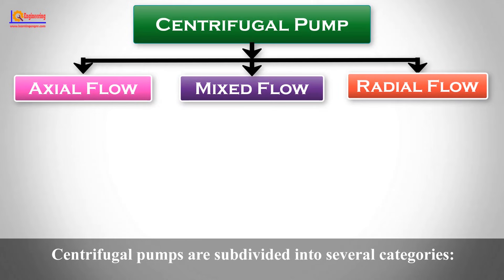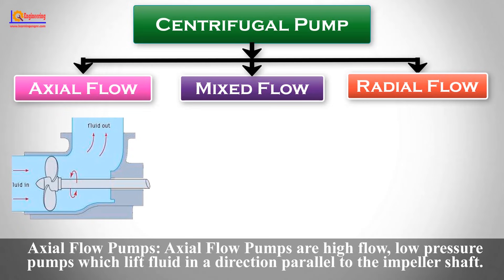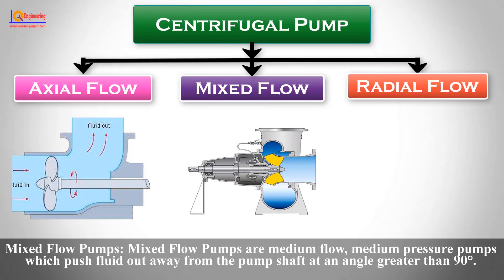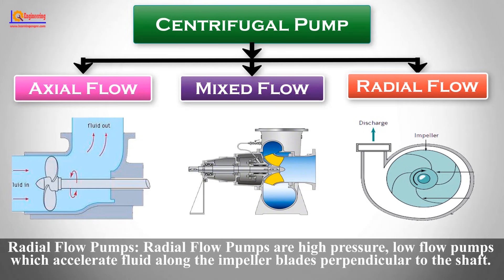Centrifugal pumps are subdivided into several categories. Axial Flow Pumps are high flow, low pressure pumps which lift fluid in a direction parallel to the impeller shaft. Mixed Flow Pumps are medium flow, medium pressure pumps which push fluid out away from the pump shaft at an angle greater than 90 degrees. Radial Flow Pumps are high pressure, low flow pumps which accelerate fluid along the impeller blades perpendicular to the shaft.